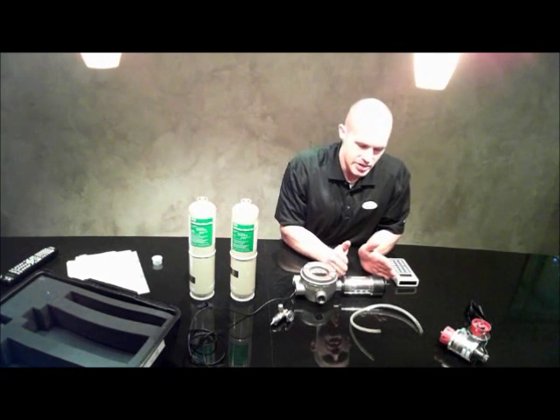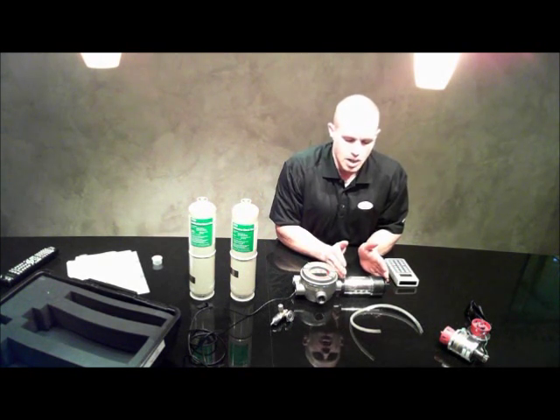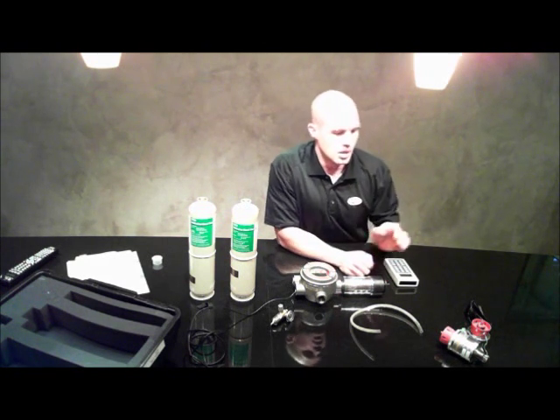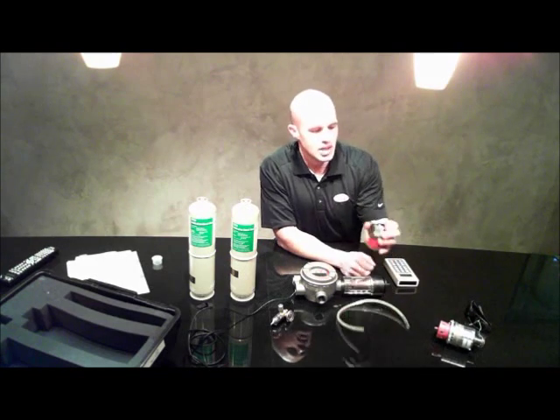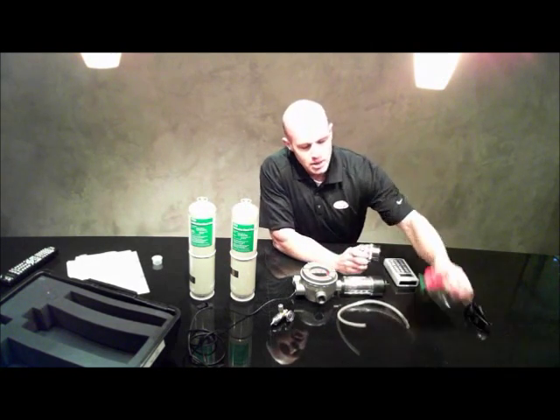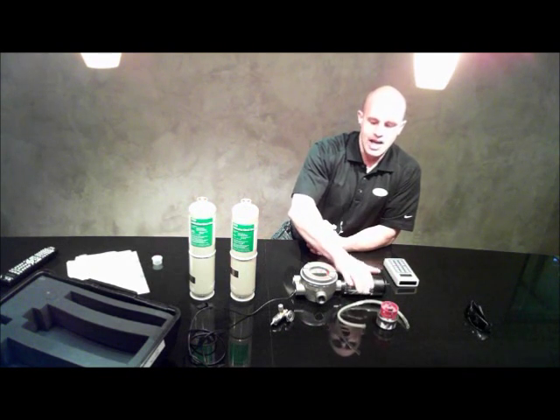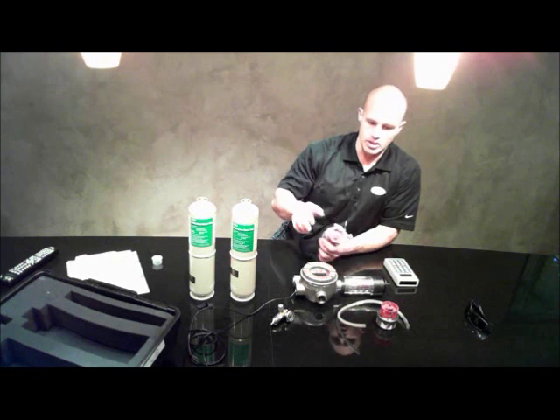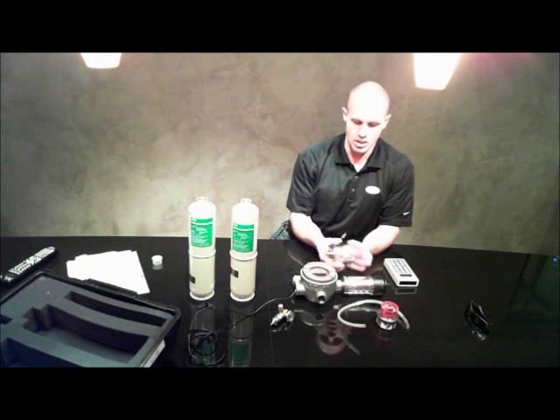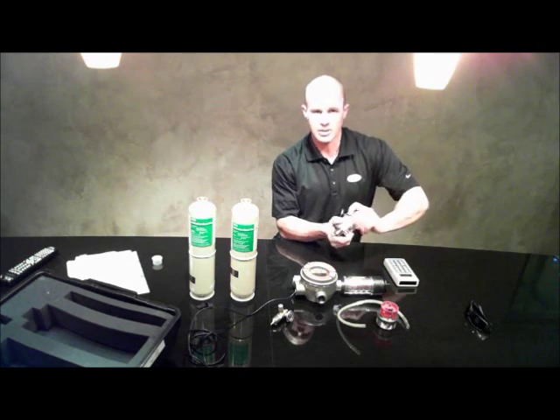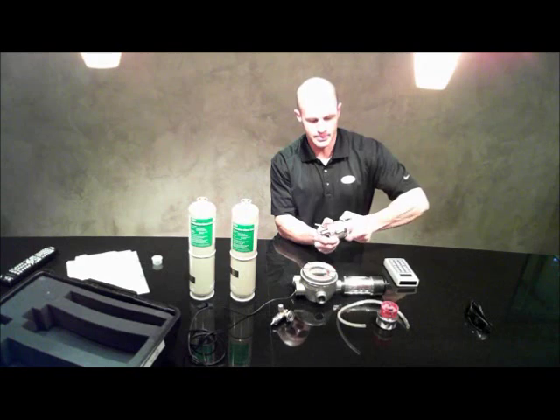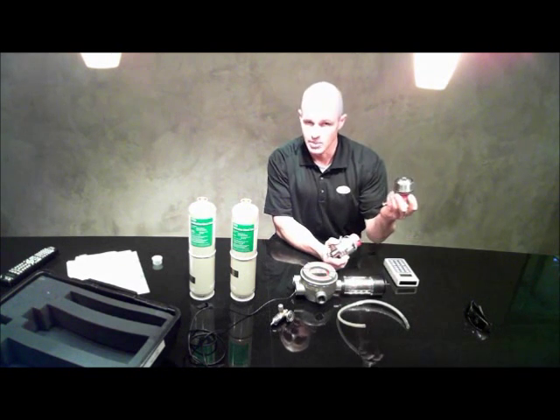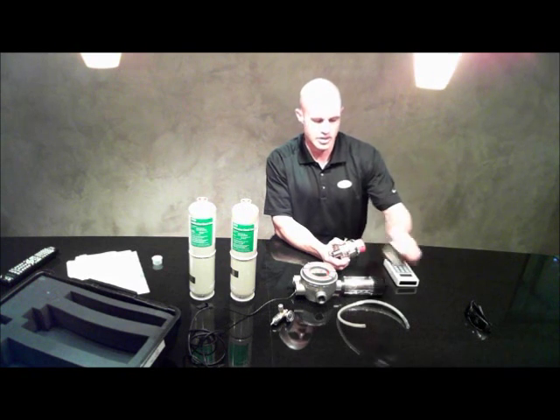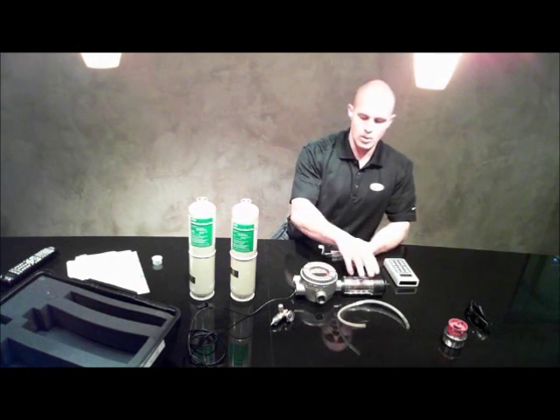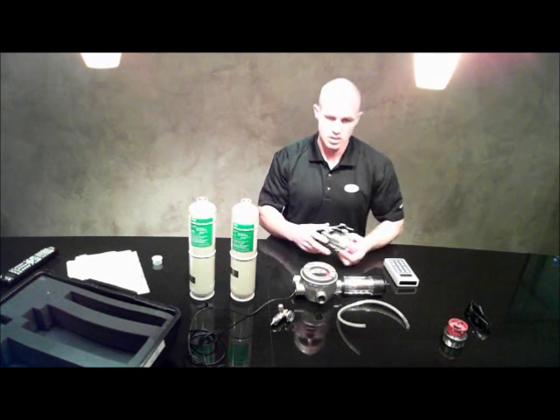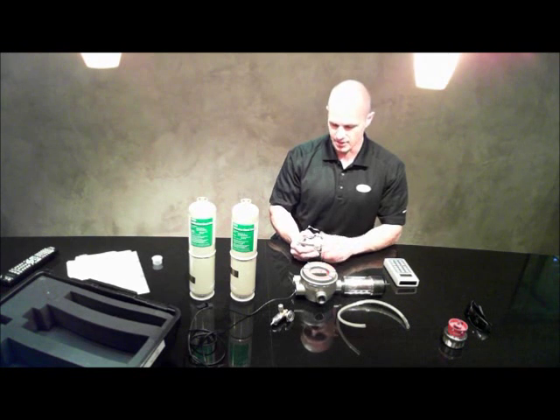Then over here, this is an infrared style sensor common to CO2, propane gases, and methane. These are more the electrochemical or catalytic bead style. So instead of having this attached to either the remote housing or directly onto the transmitter here, you would have this mounted on, and then your sensor screws into this housing. So this is one of these sensors, either electrochemical or catalytic bead, that's just threaded into this housing here, but again would either connect to a remote housing from this or directly onto the transmitter, depending on the nature of the gas that you're detecting.